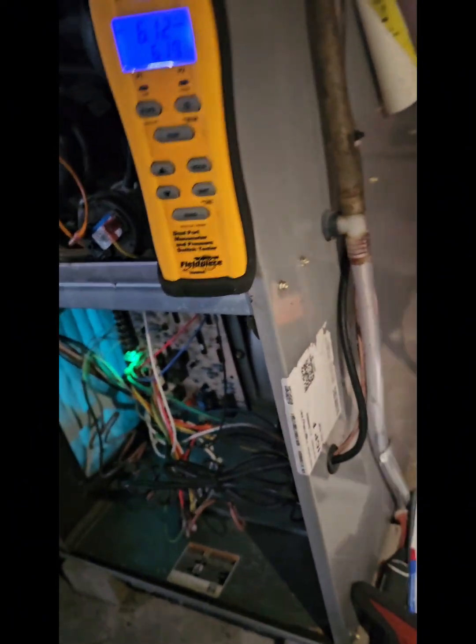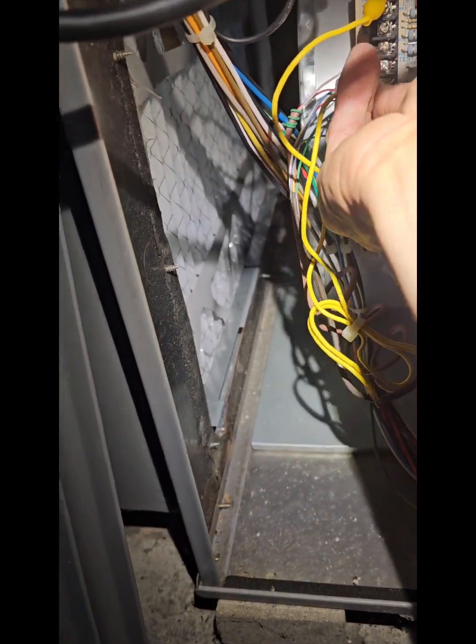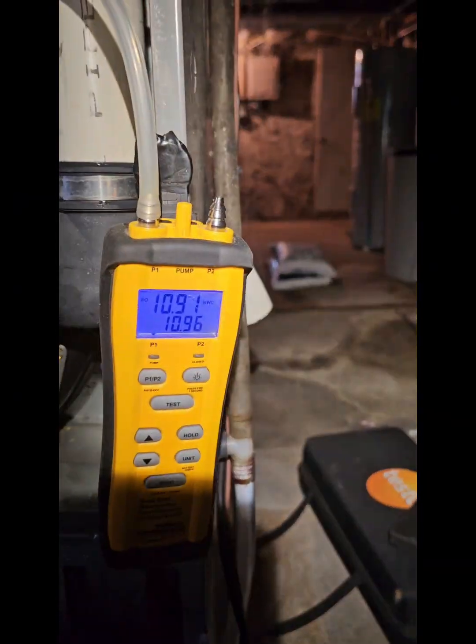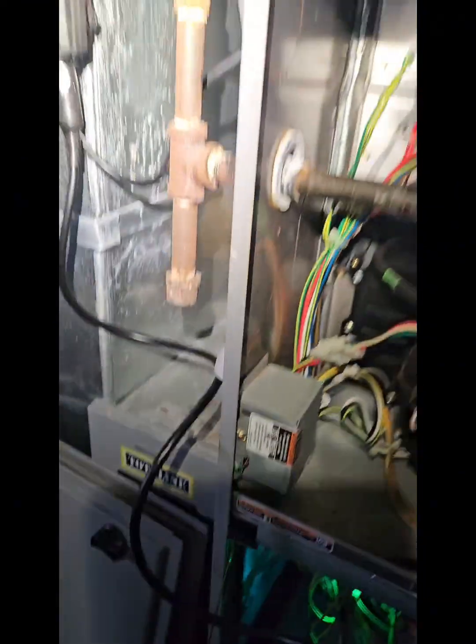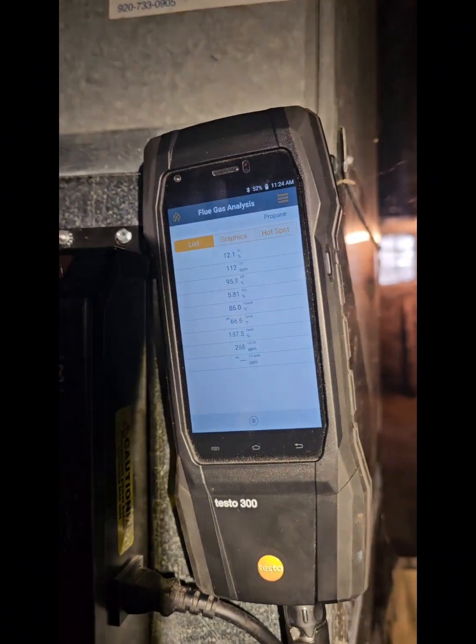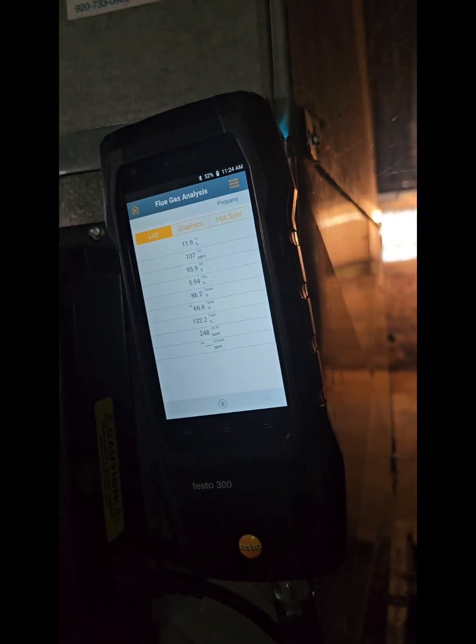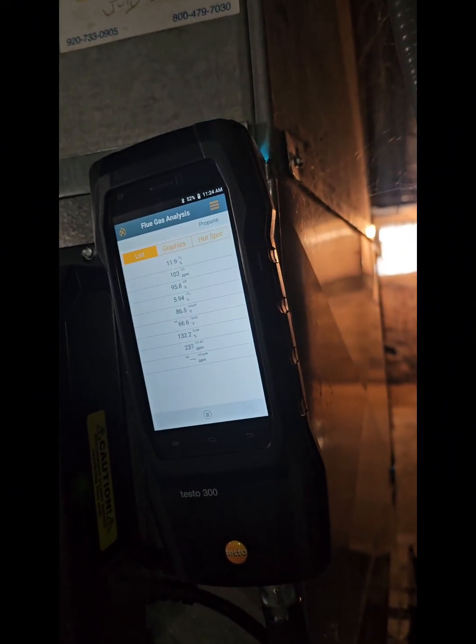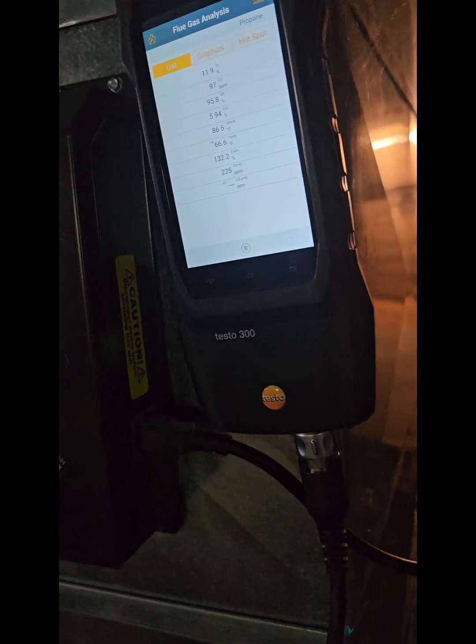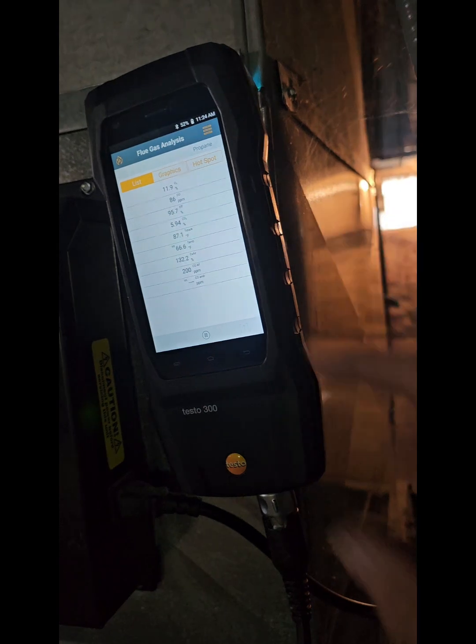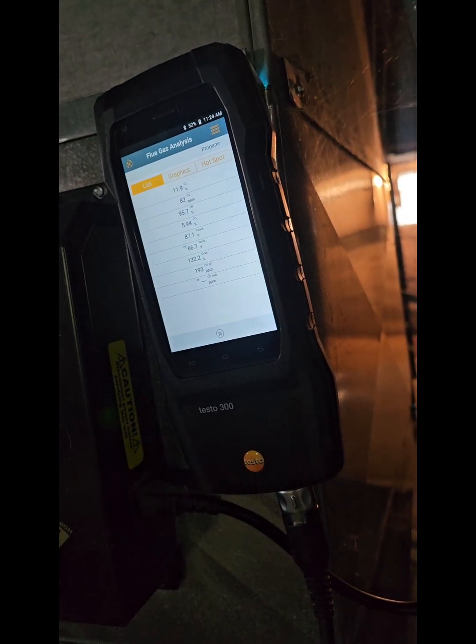Let's put it into high fire and see what it looks like in high fire. Go to W2. W1. Okay, our gas pressure has gone up to 11 inches, right where it's supposed to be, and our combustion analysis is dropping. It's dropping a little bit. See how far it goes down. The excess air also has dropped, but did not drop below 100. That's a little bit interesting.